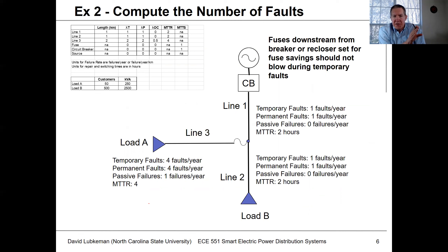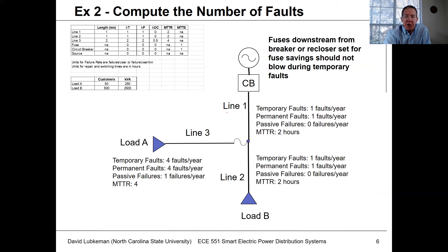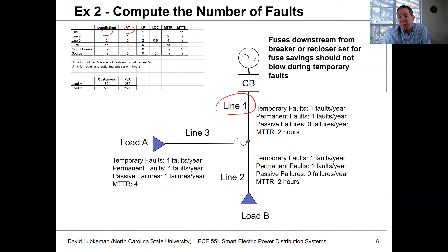The approach is to start by computing the various contingencies and the number of times they occur per year. For example, with three line segments, I'll have contingency locations for lines one, two, and three — covering temporary faults, permanent faults, and passive failures. For line segment one with a temporary failure rate of one per kilometer per year, multiplied by the line length, that gives me one fault per year. Similarly for permanent faults.